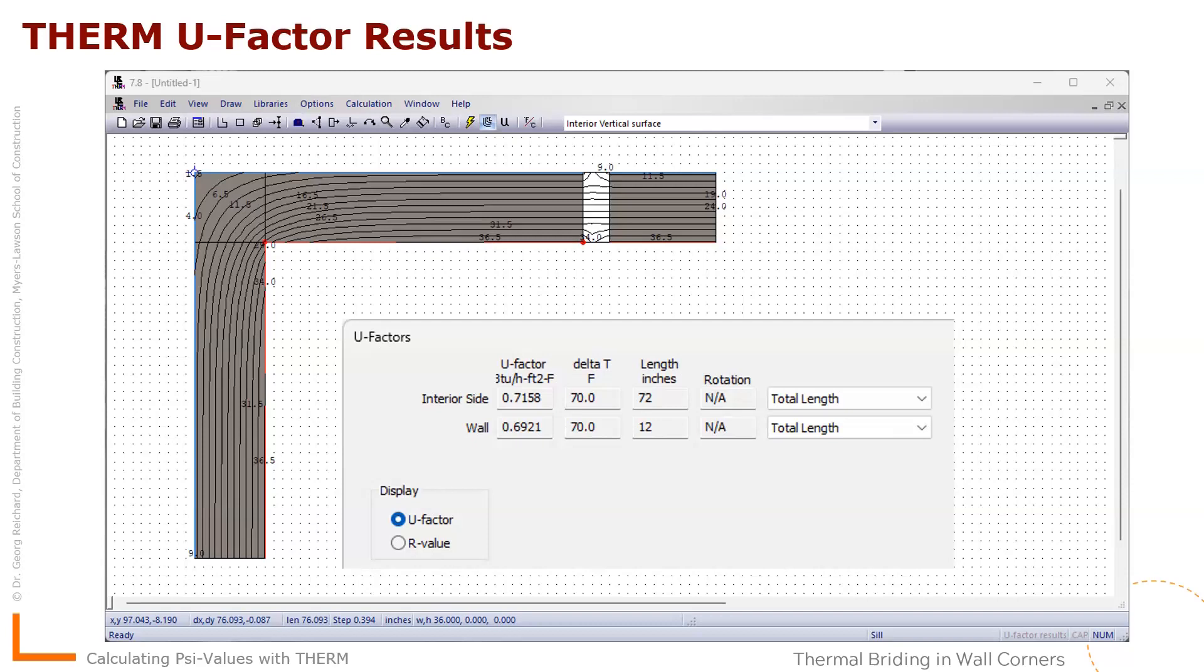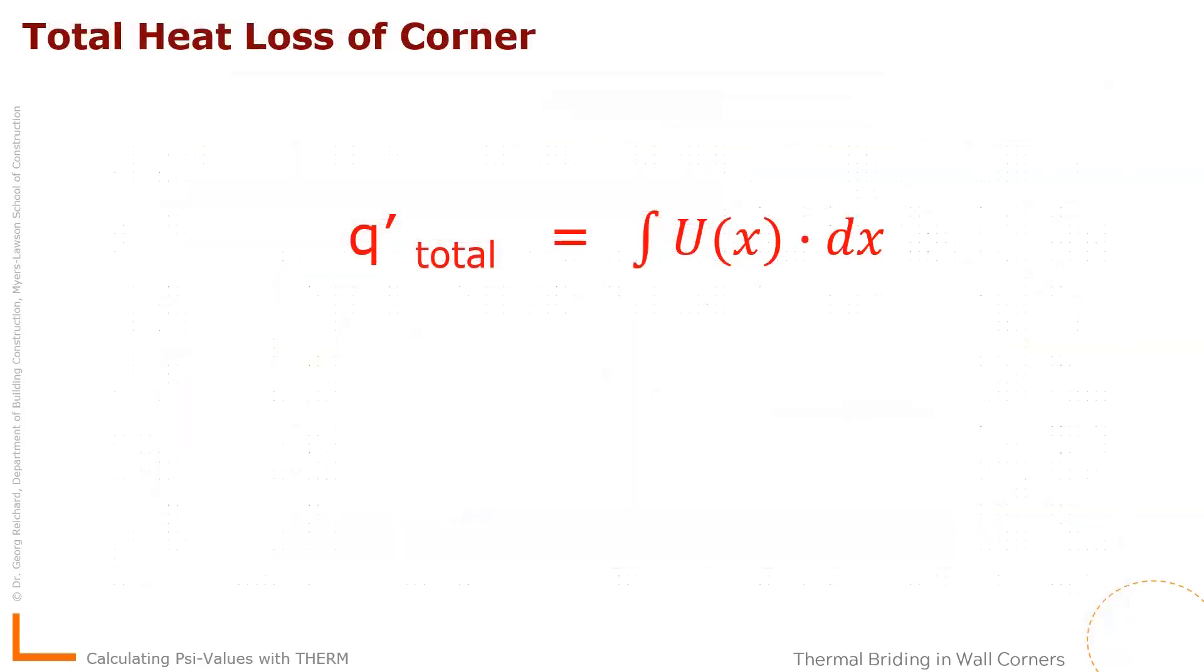So what we want to know is what's the total heat loss across the corner. And we can write this as the integration of the U value of the conductance at a certain point along our surface over the length of those surface. Now, Therm produced that result as average of this function. And we can write this as a U value, the average U value that Therm spits out over the length because we walk along the X axis. The X coordinate is along the edge that we walk. So that's what we call the total length that we use there.